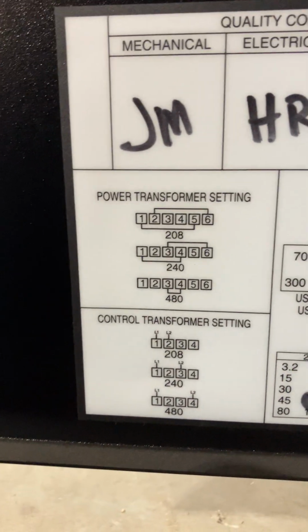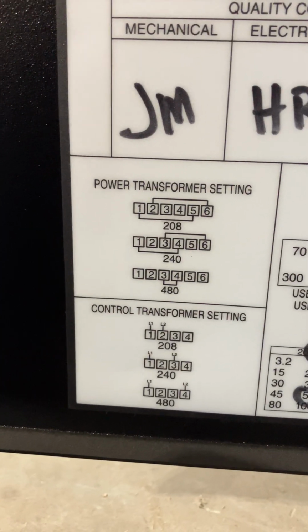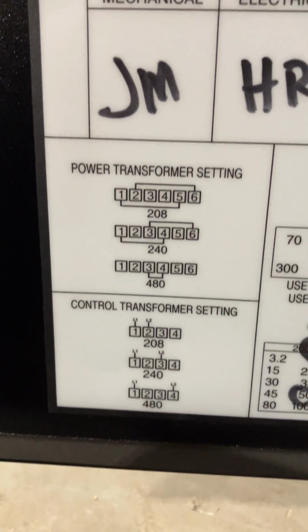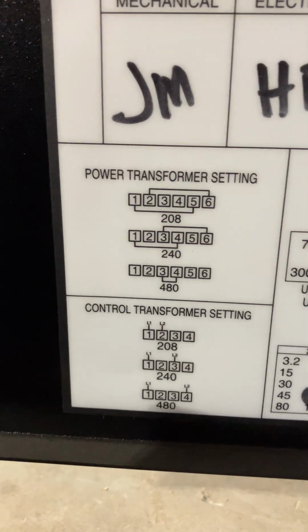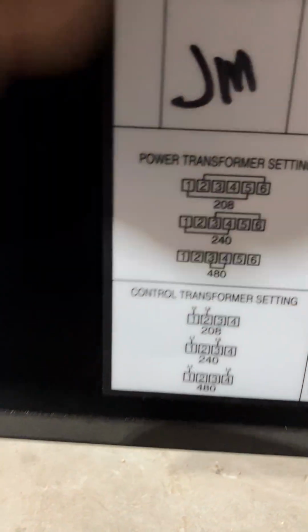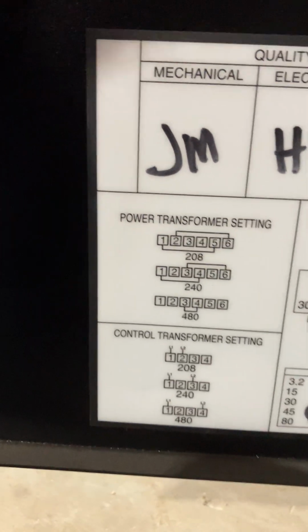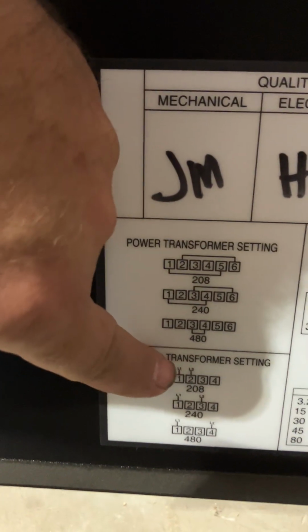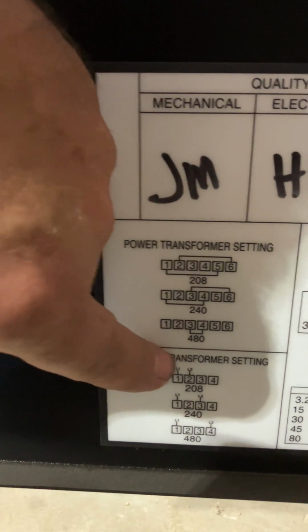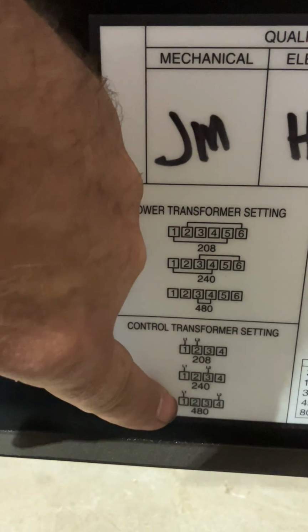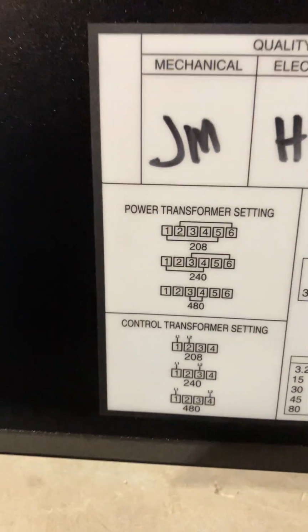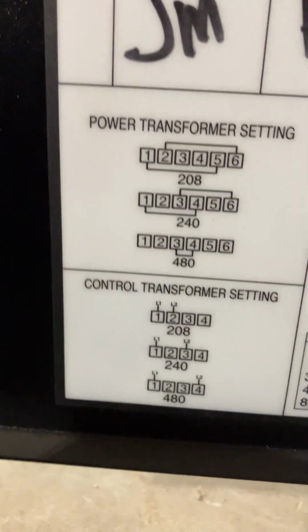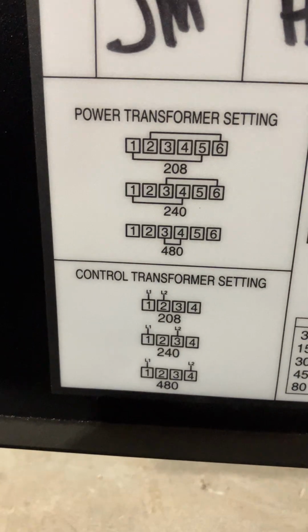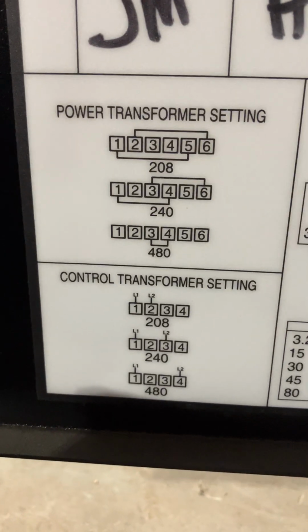Then on the control transformer, it says again 208 volts, 240 volts, and on the bottom 480 volts. Again, we're feeding this with 480 volts, and whatever the control transformer is, probably 120, I don't know. It probably says somewhere in here, but I don't really care. All I know is as long as we hook these up right, it'll work. We're not going to hook it up the way it shows for 208. We're not going to short it the way it shows for 240. We are going to hook it up, because it's not shorting this time for the control transformer. We're just tapping it, according to 480.